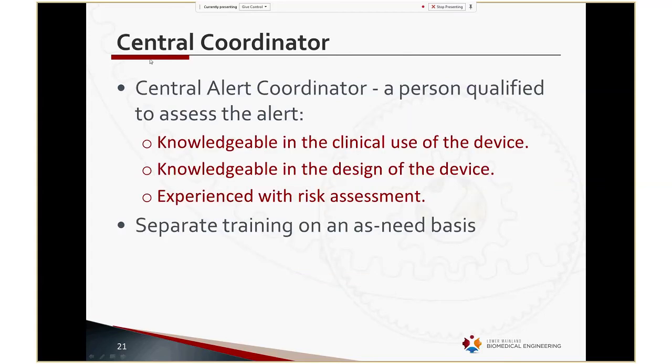So who could actually be a central coordinator? Really, again, this could be anyone across the lower mainland within biomed. We were just looking for people that would be knowledgeable in the clinical use of the device, knowledgeable in the design of the device, and have some experience with risk assessment. So if an alert is identified as needing a central coordinator, we'll ask for volunteers during that weekly call.